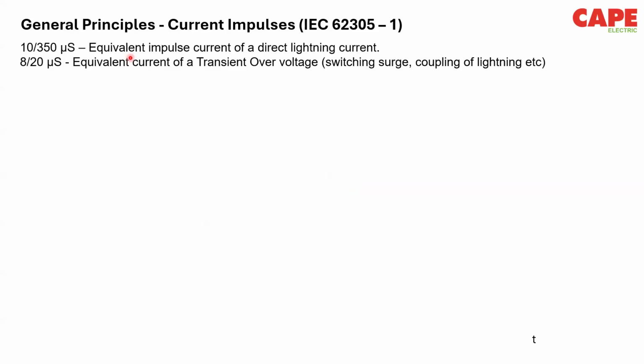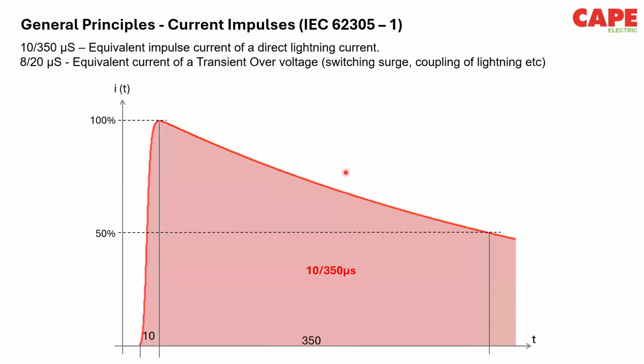Now, before I jump to this topic, let me explain some basic principles about SPDs. We have two current wave shapes. One is 10 by 350 and the next one is 8 by 20. 10 by 350 is for direct lightning current, and 8 by 20 we consider for coupled or indirect lightning currents and switching surges. A 10 by 350 looks something like this. At 10 microseconds from zero, it will reach 90 to 100 percent of its peak surge current. So if it is 100 kA, at 10 microseconds it will reach 100 kA. At 350 microseconds, it will reach half of that, so 50 kA.